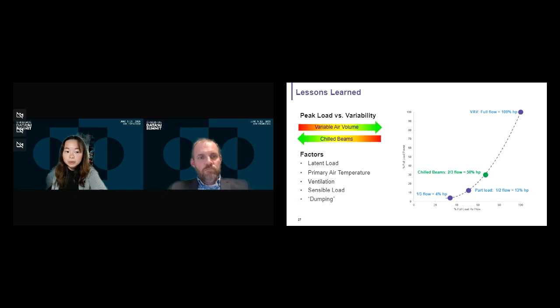So this is our overall concept of a dedicated outside air system. It is not something we commonly use for data science building. It is something we use more often for a hospital building or a wet lab building because the amount of reheat we need for those space. But the intention for us to use for this facility is to draw bottom out of airflow, meaning that we want a really, really low airflow per square foot for this building as a benefit to decrease the floor-to-floor height requirement, to minimize the shaft and penthouse requirement for a more efficient net to gross ratio on the building square footage, and also to make the overall energy performance more efficient.